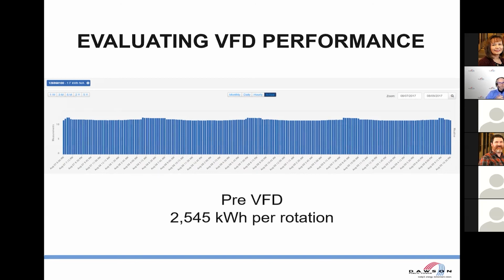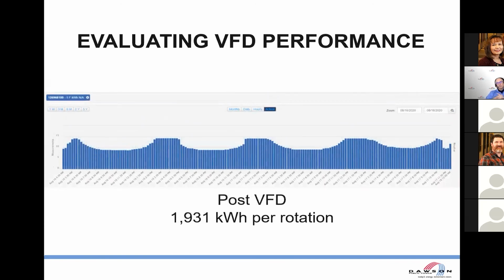Now let's look at how we can improve this system. What if we add a VFD to a corner arm system? Now our pattern looks quite a bit different. The valleys are when the corner arm is pulled in and the end gun isn't running. Before, energy consumption was way up top -- the system was running full out, maximum power all the way around the full rotation.